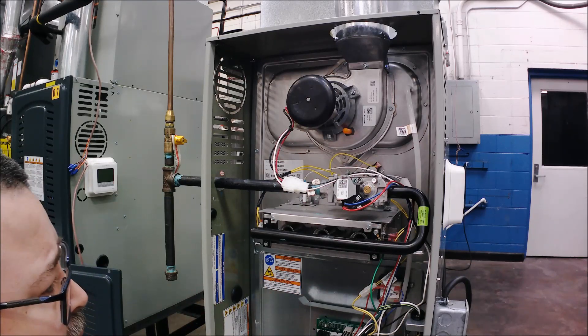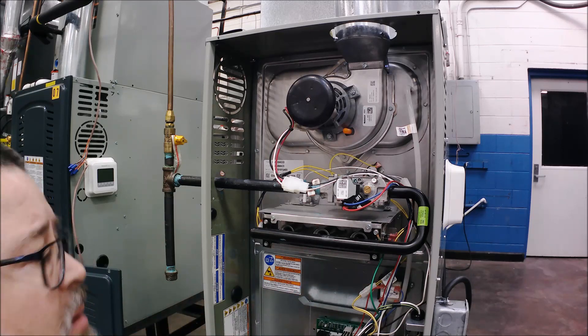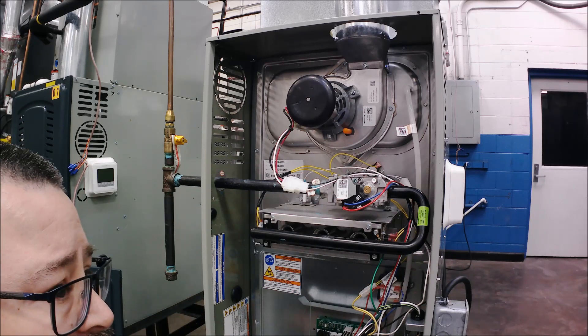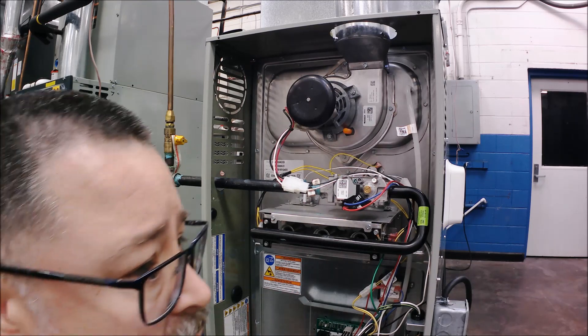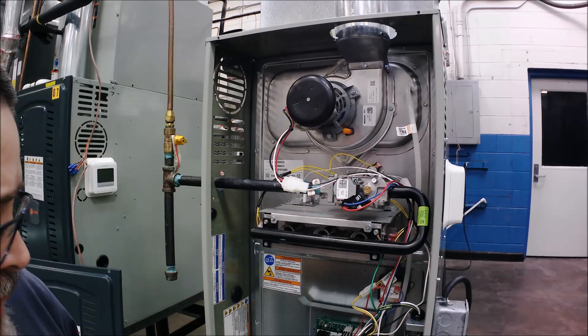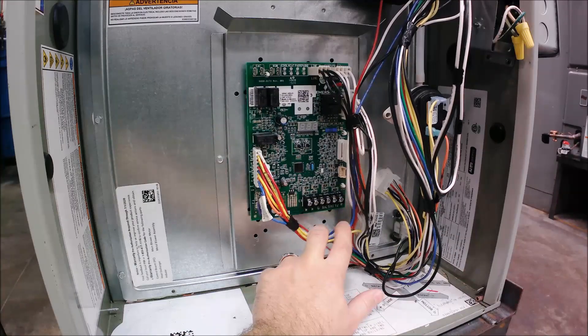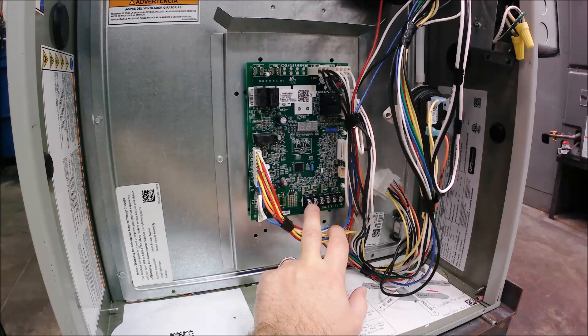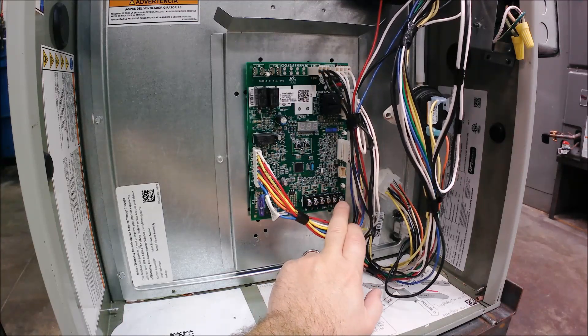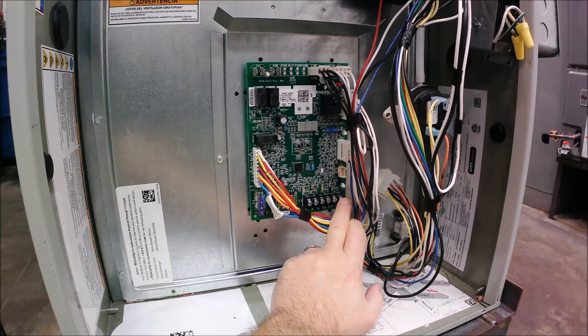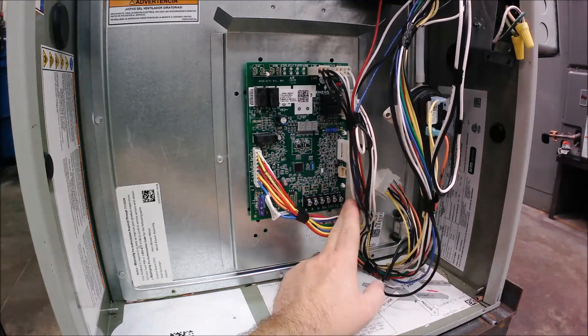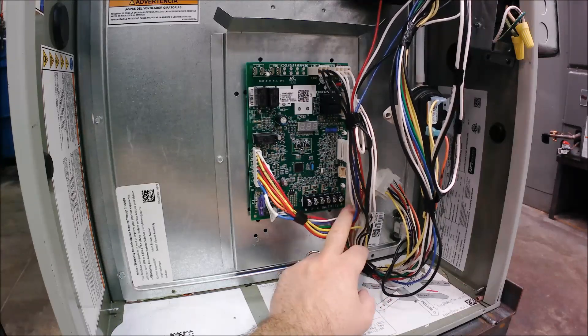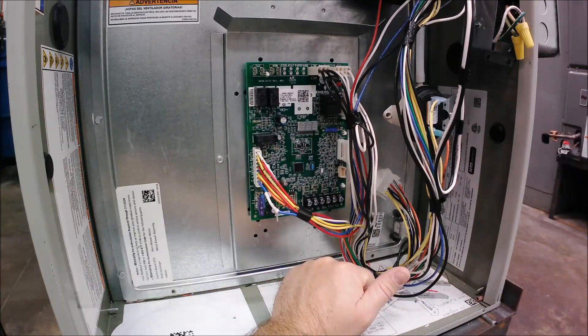Down here on the board they give you a terminal block with W, R, G, common, Y, and Y2. Just because they give you all these terminals doesn't mean you have to wire them all. We've identified we only have a heat-only unit with no air conditioning.